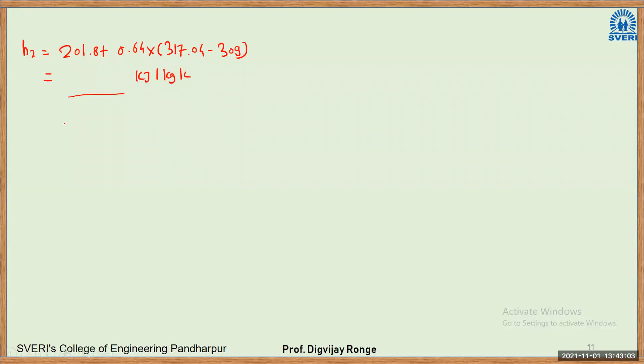So H2 will be equal to H2 dash, which is 201.8, plus Cp, which is 0.64, into T2. T2 we have calculated as 317.04, minus T2 dash, which is 309. So calculate H2. This will be in kilojoule per kg Kelvin. And then easily you can calculate the COP also. How much? 206.94. Okay, great. So the enthalpy calculated by you is 206.94.